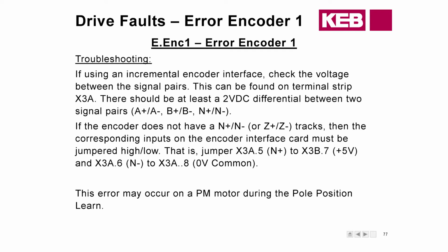Also, another note with this is that some encoders feature a 3rd channel. Sometimes they call it an N channel, Z channel. I've seen O. That is something to be aware of. If they do feature that, and the print indicates that you wired it up, then yes, follow the print. If they don't have that, what you need to do is jumper out our 3rd track. We call it an N track, but you need to jumper that out on our end.